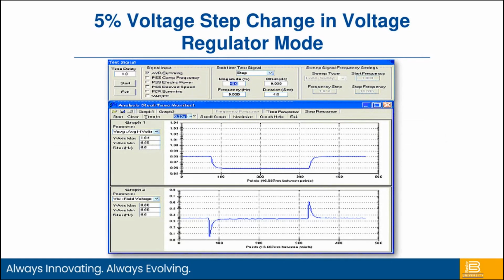Here is a strip chart recording of a 5% step change. So it's just showing the reaction out of the machine and what our goals are while we're tuning these things. So at the top is actually our generator output voltage, and at the bottom is showing the output of our voltage regulator. So you can see I'm going to do a step change. I'm going to ask for a reduction in voltage. Our field voltage drops down, and then as the voltage starts to collapse, it starts to come back up to recover to give us a nice transition.